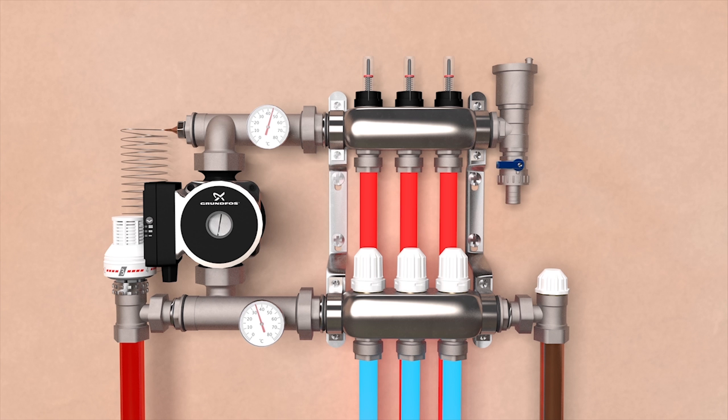The water now flows one of two ways. If the thermostatic blend valve is letting warm water into the system, then cooler water needs to be released from the manifold to make room for the warm water. The cooled water will then exit through the boiler return valve and back to the boiler for reheating.